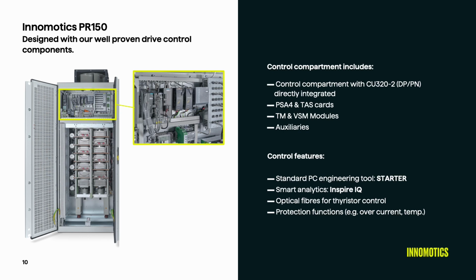Let's have a look into that product. We are using our standard well-proven components from our Innomotics medium voltage drives family. Our CU320-2, our power stack adapter with TAS cards for controlling the thyristors. We are using standard terminal modules, voltage sensing modules, whatever is needed for the control of that system. Having some auxiliaries, fans, heaters, whatever is needed. Important are also the control features. We are just using our engineering tool STARTER, which is well known for all other Innomotics medium voltage drives. And of course, as we are looking for a future design, we have the smart analytics, what we call Inspire IQ right now. And then standard optical fibers for control of the thyristors. All proven design from our Innomotics medium voltage drives.